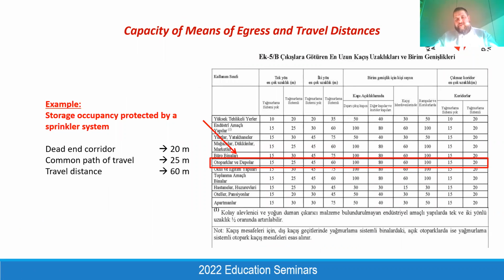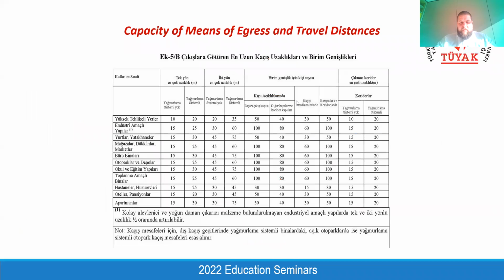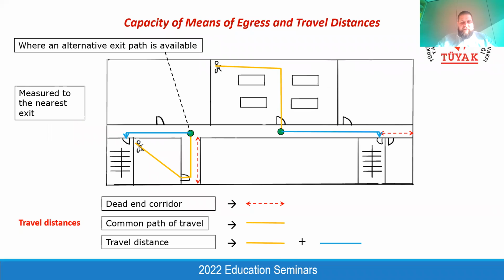if we are comparing the storage occupancy situation, just let me annotate it. We have two columns on this table. The right one is for the building protected by a sprinkler system, and the left one is for the building that is not protected by a sprinkler system. As you see, the common path of travel is 25 for the sprinkler building, but only 15 for the non-sprinkler building. If I come to the previous slide, you can see that these yellow ones become 25 for the sprinkler building. But if we don't have sprinkler protection within the building, it's only 15 meters.